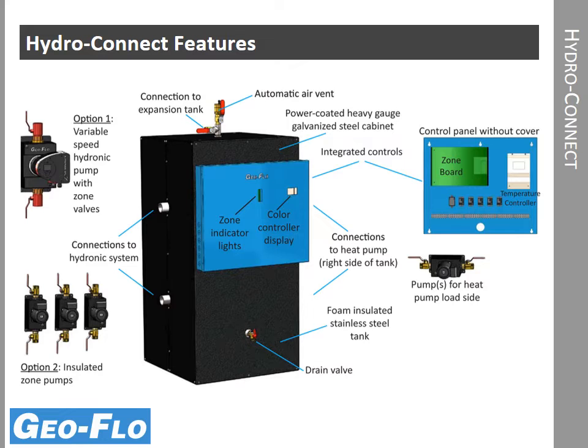With option 1, you'll see the variable speed pump, and that's coupled with zone valves, which we'll show on a slide later on. On the lower left-hand corner, option 2 would include insulated pumps for each of the zones. And then on the right-hand side of the slide, you'll see an insulated pump labeled "Pumps for Heat Pump Load Side." That pumps the fluid from the heat pump over to the buffer tank. So this would be a typical system.